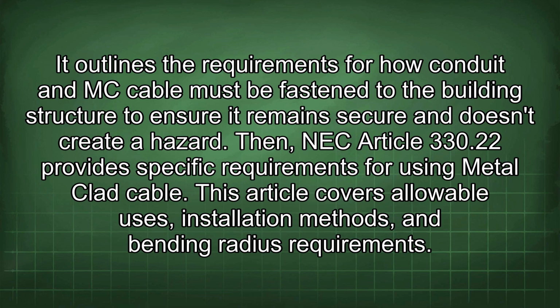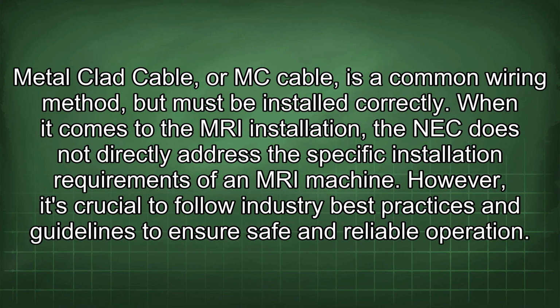Then, NEC Article 330.22 provides specific requirements for using metal-clad cable. This article covers allowable uses, installation methods, and bending radius requirements. Metal-clad cable, or MC cable, is a common wiring method, but must be installed correctly.